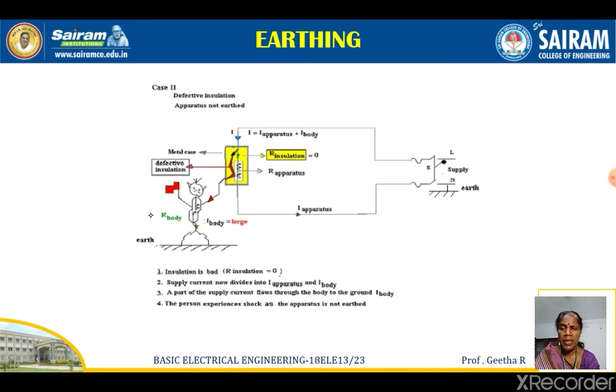Case 2. Here there is defective insulation and the apparatus is not earthed. In the previous case, it is good insulation, but the apparatus is not earthed. With the apparatus not earthed, if there is any defective insulation, there is a possibility of current flowing through the human body, causing shock to the human being. Here you can understand the importance of the earthing.